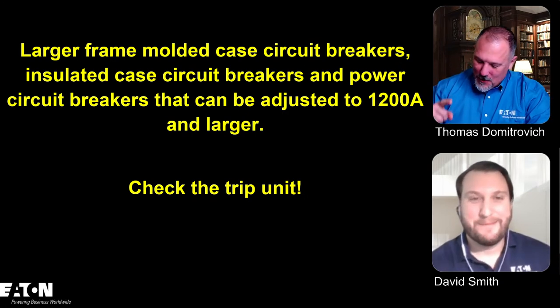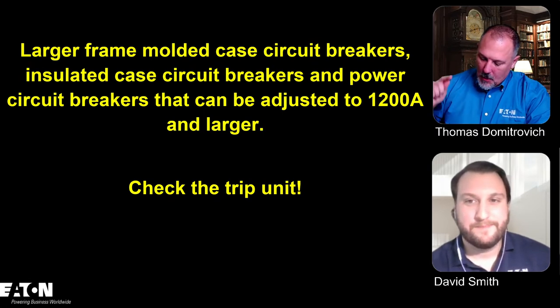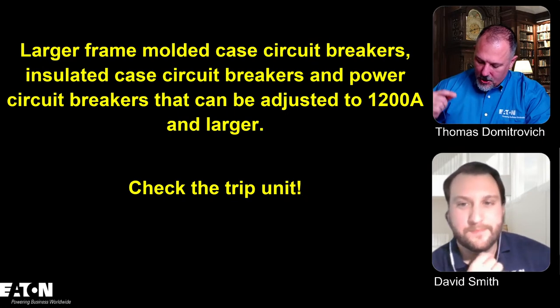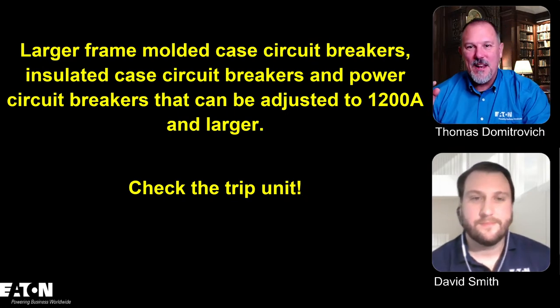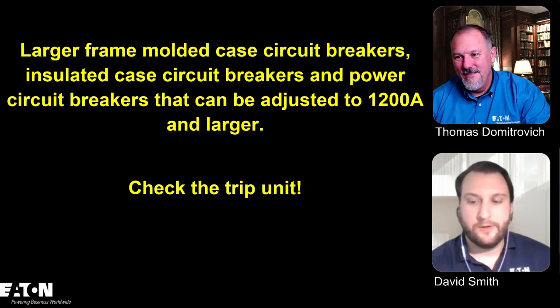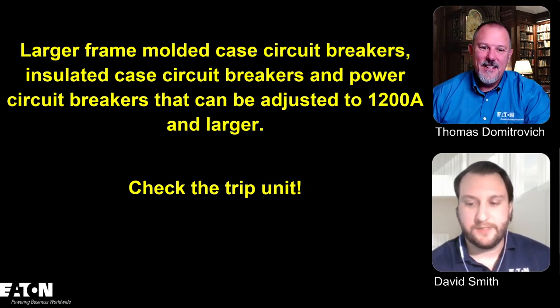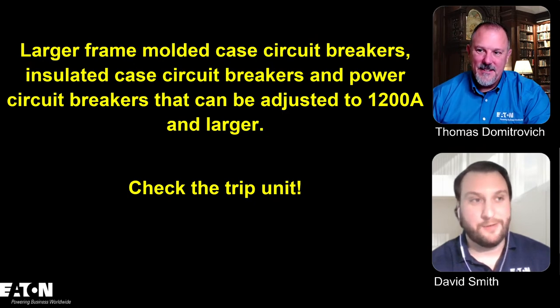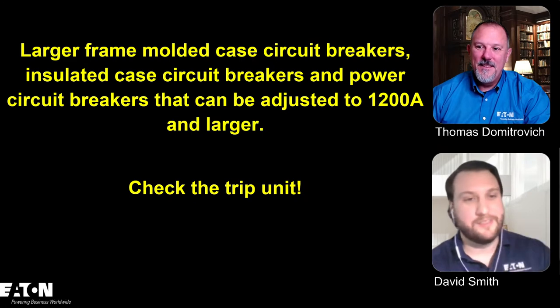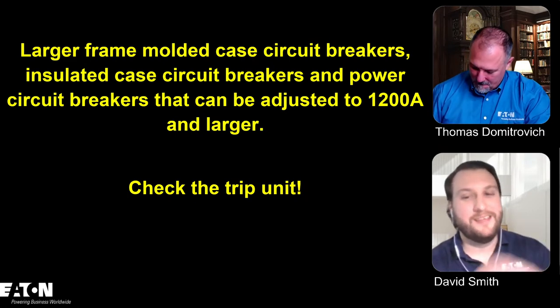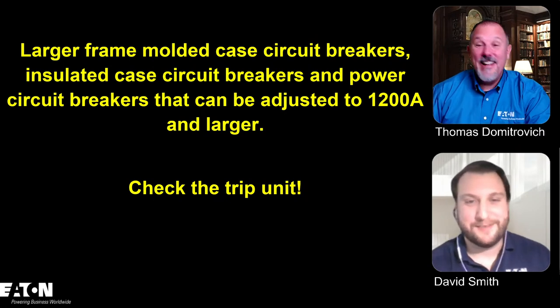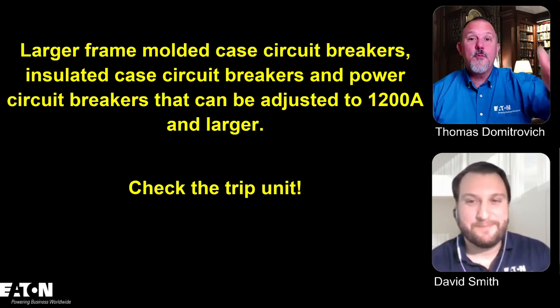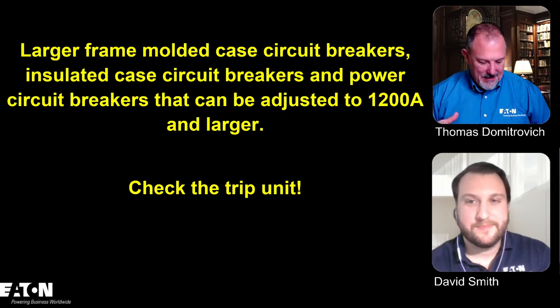240.1 says parts 1 through 7 of this article provide the general requirements for overcurrent protection and overcurrent protective devices not more than 1,000 volts. So that would include part 7 having to do with cartridge fuses and stuff like that, right? Yes. So that includes 240.67, which is not what this video is about, but it's going to be the sister video I'm sure we'll eventually get to. Exactly. So parts 1 through 7 are 1,000 volts and less. So what's part 8? Let's take a look.